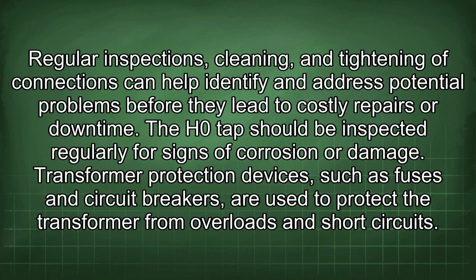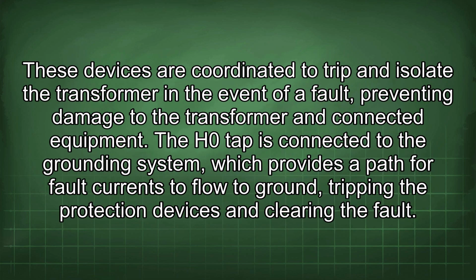Transformer protection devices, such as fuses and circuit breakers, are used to protect the transformer from overloads and short circuits. These devices are coordinated to trip and isolate the transformer in the event of a fault, preventing damage to the transformer and connected equipment. The H0 tap is connected to the grounding system, which provides a path for fault currents to flow to ground, tripping the protection devices and clearing the fault.